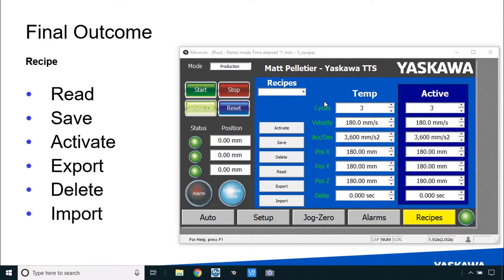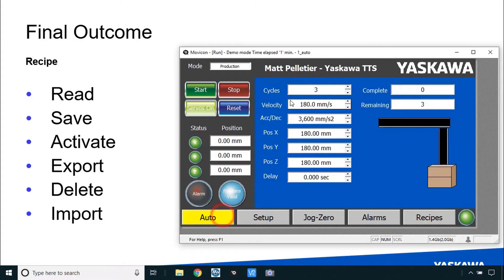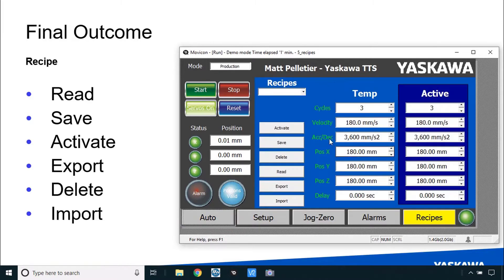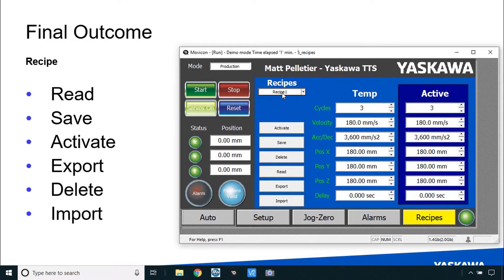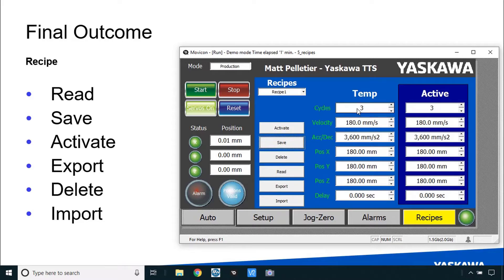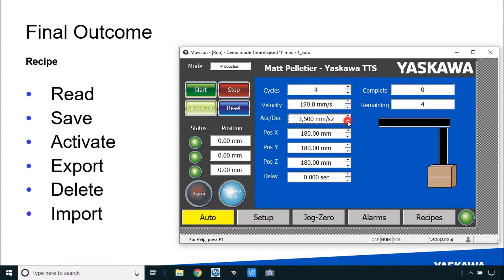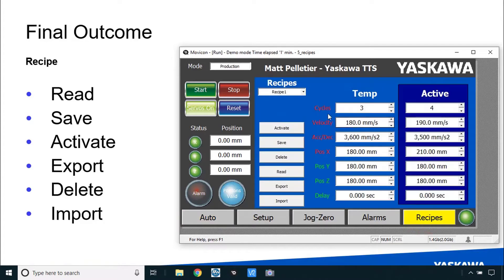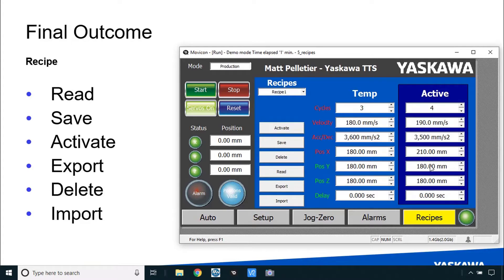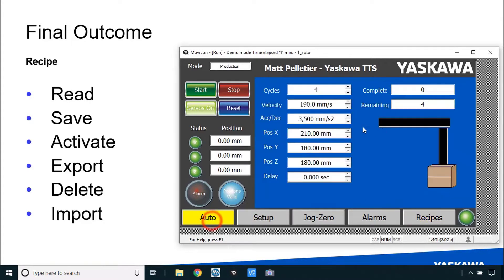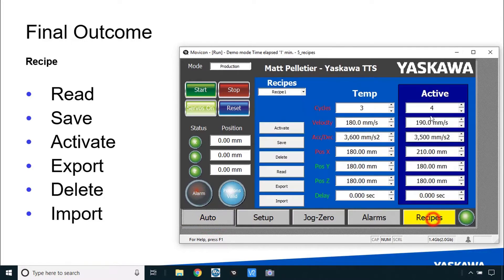A recipe means you can save a set of data from the automatic production screen into the device itself. All you do is type in, for example, recipe 1, and when I hit save it saves this temp data into the HMI device. The user could be in the auto screen and perhaps change some of the settings. Those settings could then be saved in the recipe screen by simply reading in what we're calling those active values. Those are the same values from the auto screen.